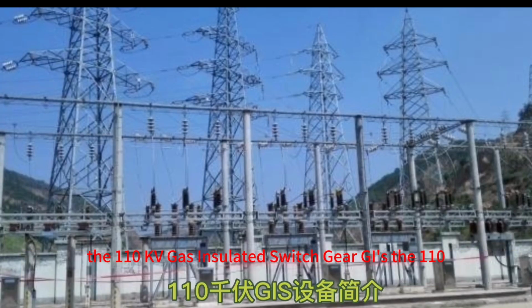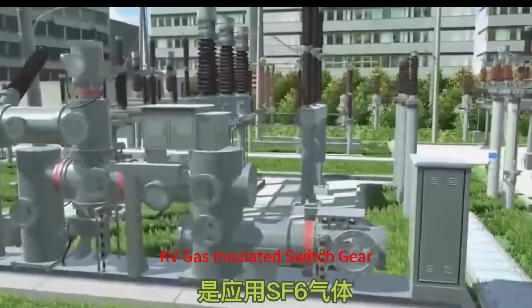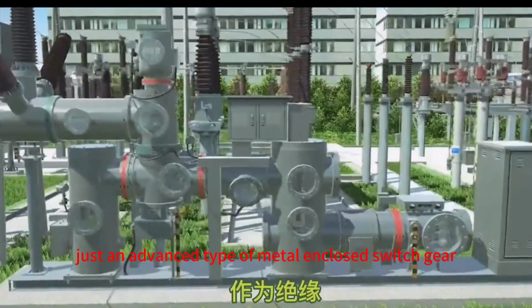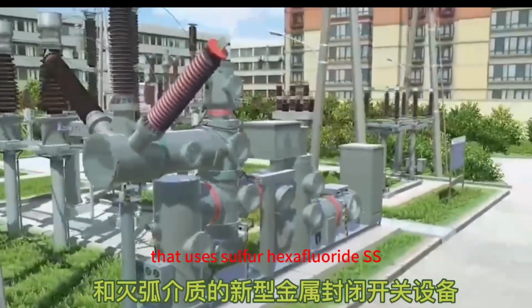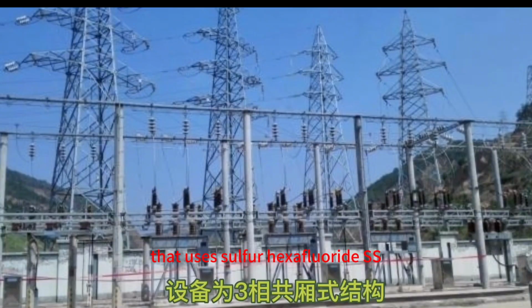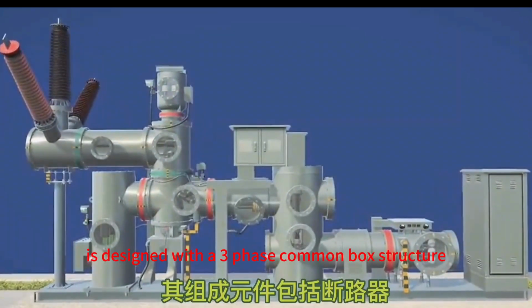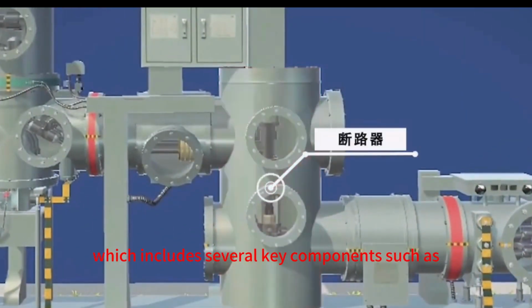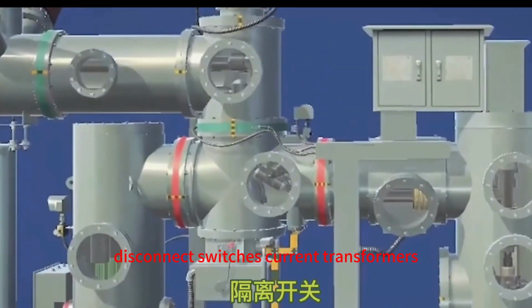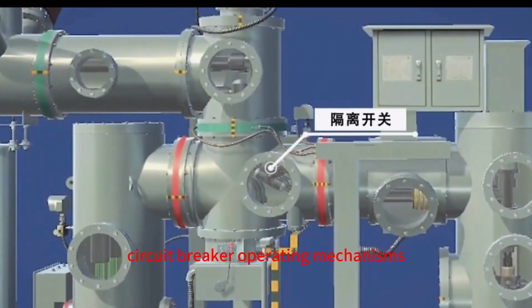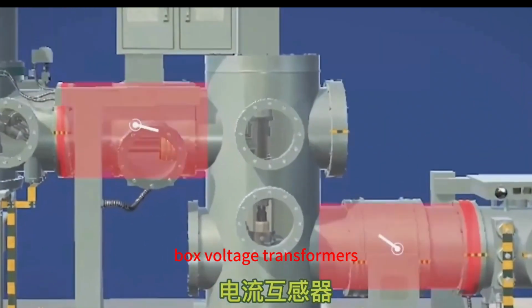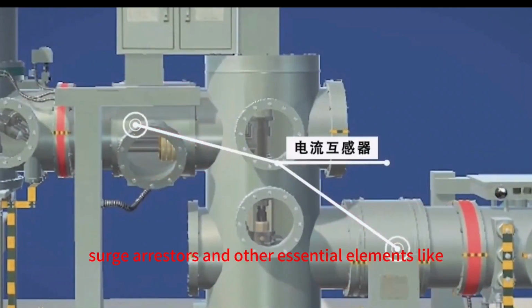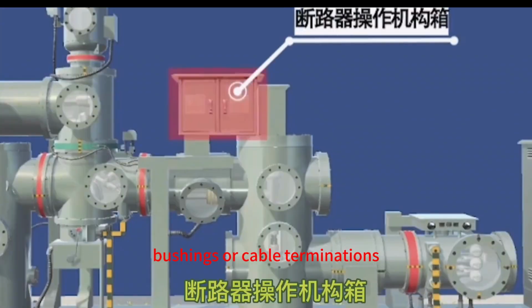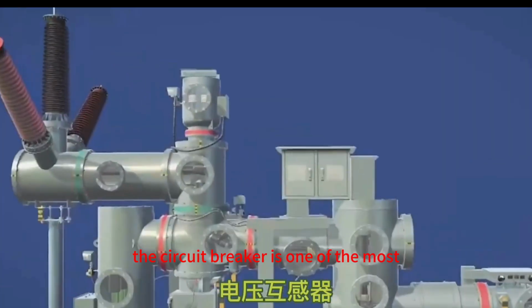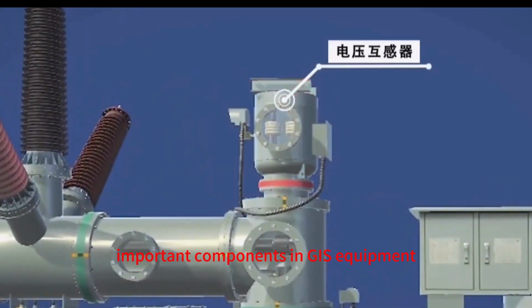The 110 kV gas-insulated switchgear, GIS. The 110 kV gas-insulated switchgear is an advanced type of metal-enclosed switchgear that uses sulfur hexafluoride, SF6. This high-voltage equipment is designed with a three-phase common box structure, which includes several key components such as circuit breakers, disconnect switches, current transformers, circuit breaker operating mechanisms, box voltage transformers, surge arresters, and other essential elements like bushings or cable terminations.